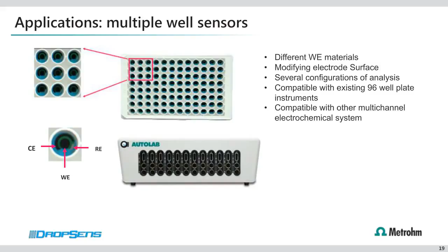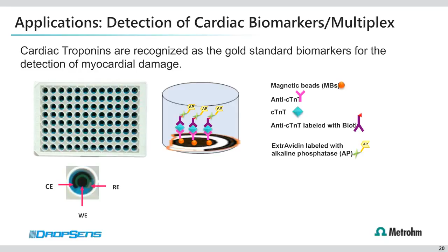To illustrate this, here is an example of cardiac biomarker detection. In each well, an immunological reaction is carried out for the detection of cardiac troponin. An appropriate selection of detection antibodies gives us selectivity to the analyte, and the electrochemical detection method, detection through the alkaline phosphatase system, provides us sensitivity in the detection. Applying solutions of known concentration of the analyte in different wells and running the simultaneous electrochemical measurement of these different wells, we get the calibration plot. The correlation curve is shown in the slide with a limit of detection of 0.05 nanograms per milliliter.